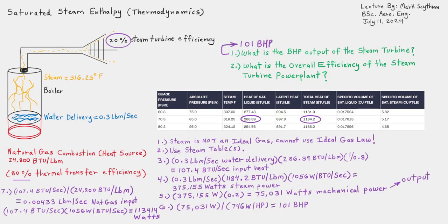We identify the output power as 75,031 watts of mechanical power at the turbine, and the input power as 113,414 watts. Dividing the output power into the input power — 75,031 watts mechanical divided by 113,414 watts of burning natural gas combustion — translates to 0.6616, or 66.2% overall efficiency.